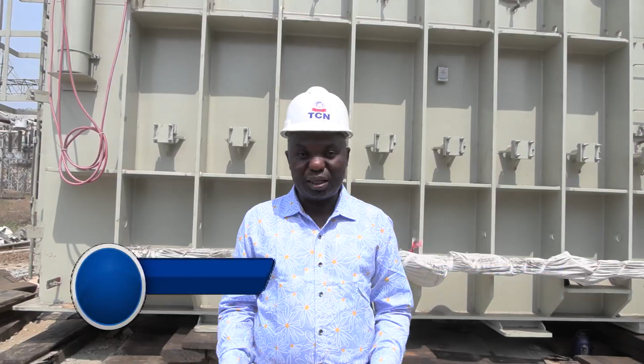The capacity of this station presently, we have 3 by 60 MVA, 132 by 33 kV, and 1 by 100 MVA, 132 by 33 kV. With this addition, we will now have 5 transformers at 132 by 33 kV, because presently we have one existing 100 MVA. As we can see, this is an additional one. We now have 2 by 100 MVA, 132 by 33 kV, and another 3 by 60 MVA transformer. You have 280 before, plus this 80 now from the 100 MVA.